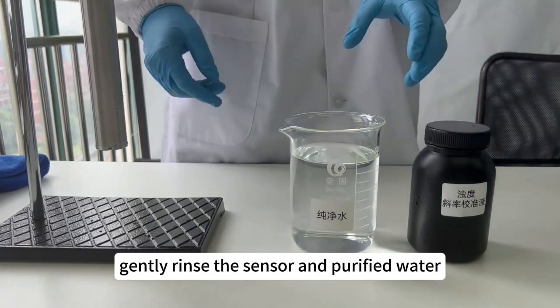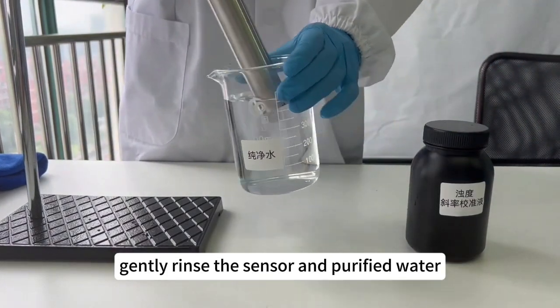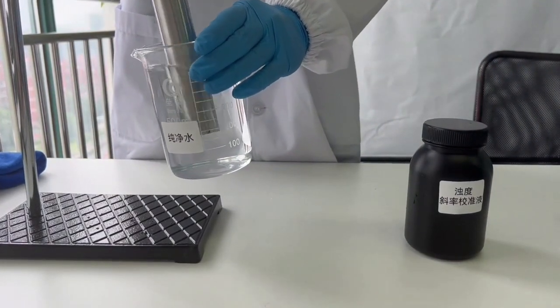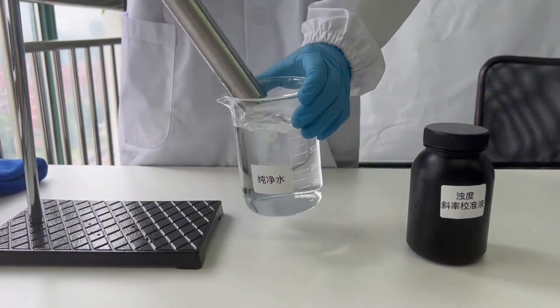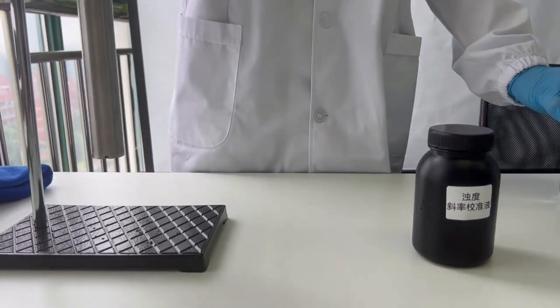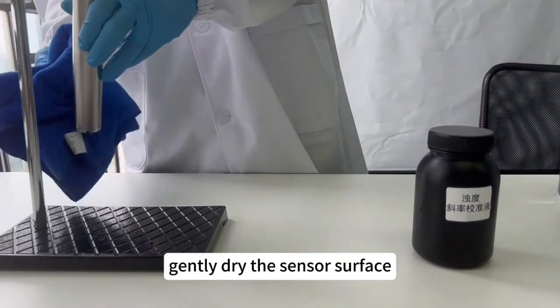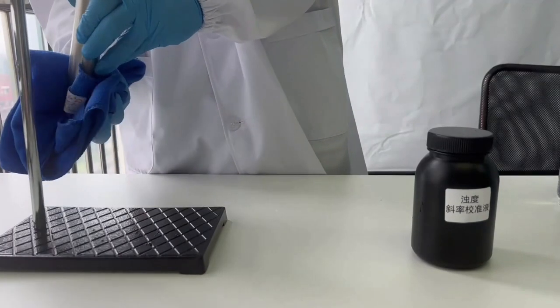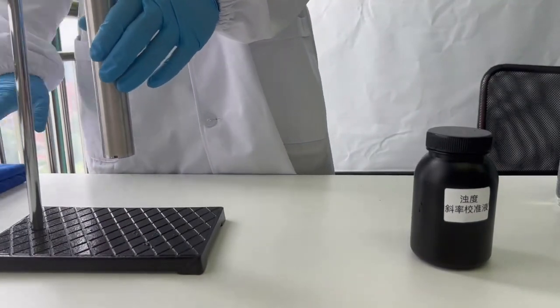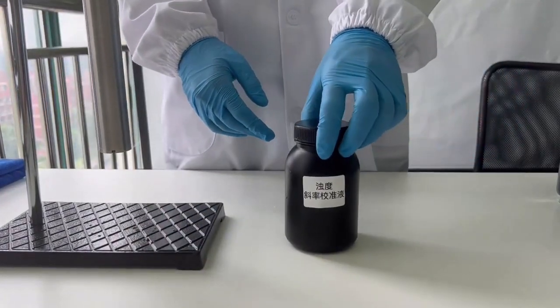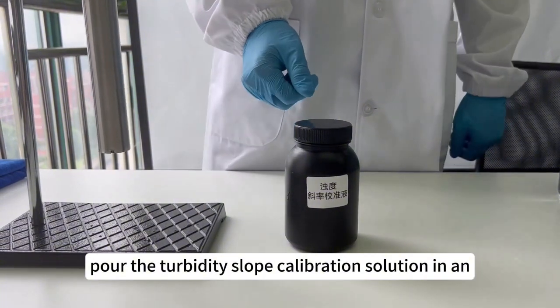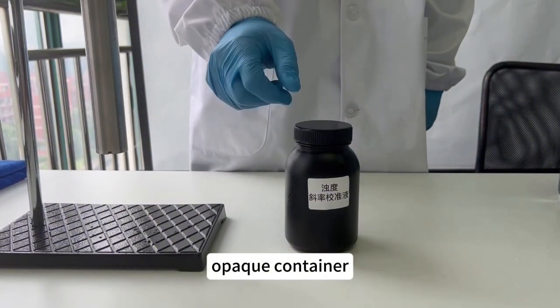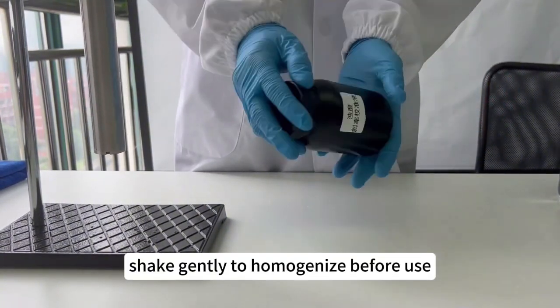Gently rinse the sensor in purified water. Gently dry the sensor surface. Store the turbidity slope calibration solution in an opaque container. Shake gently to homogenize before use.